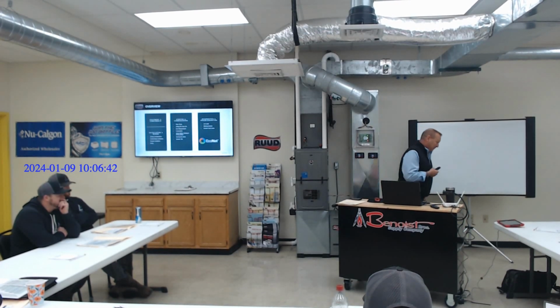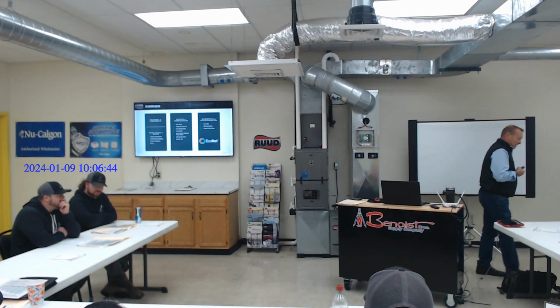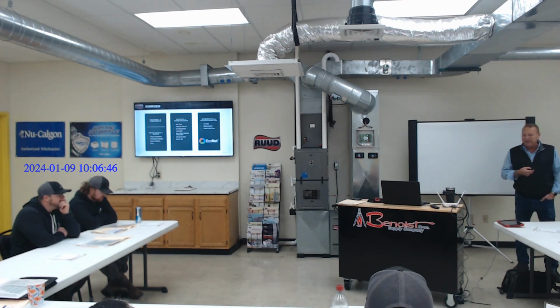I'll give you an example, and it's a pro partner, by the way. I was on a job in St. Louis yesterday. They had a 6 by 11 and a 7 by 13 floor return for a 4-ton system. So that's why I'm preaching. Sometimes it doesn't sink in. We've got to know how much return we have, because that's where we get into our biggest problem, because of the way this sets up.